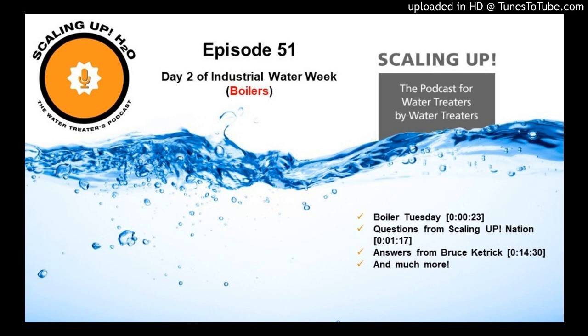As you get over 300 psi, you're going to have to look at different oxygen scavengers in particular, because sulfite is not as functionally capable of tying up oxygen at higher pressures. It breaks down into elemental sulfur. And the levels you're allowed to use start to diminish to the point where you're below 20 ppm. So some of the reducing agents such as DEHA, erythorbates, or quinones are used once you get over 300 psi and definitely have to be used over 600 psi. As a matter of fact, the more popular ones at that point are carbohydrazide and DEHA in particular.